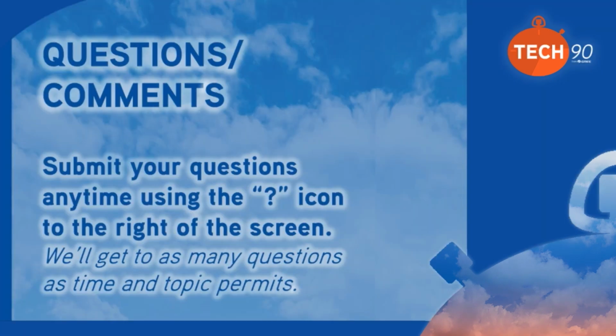All right, moving along, we've got Michael. He had a comment. He said, with spray foam houses, I have had several houses needing to heat in one room and cool in another, especially upstairs and downstairs. Well, we don't have a single phase heat recovery unit, but that would be an ideal situation to have separate systems, especially upstairs and downstairs. In a spray foam house like that, you may be better off with separate systems, so you could run cooling on one floor and heating on another if you're having problems with that.